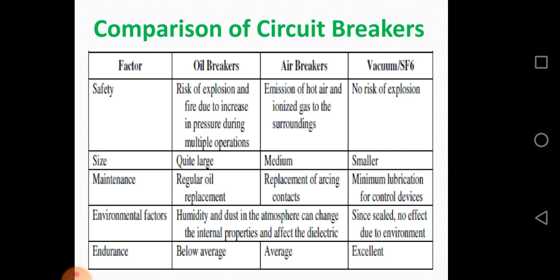Factor: size — oil circuit breaker is quite large, air circuit breaker is medium, but vacuum or SF6 circuit breaker is smaller. Factor: maintenance — regular oil replacement in oil breakers; replacement of arcing contacts in air circuit breakers; minimum lubrication for control devices in vacuum or SF6 circuit breakers.